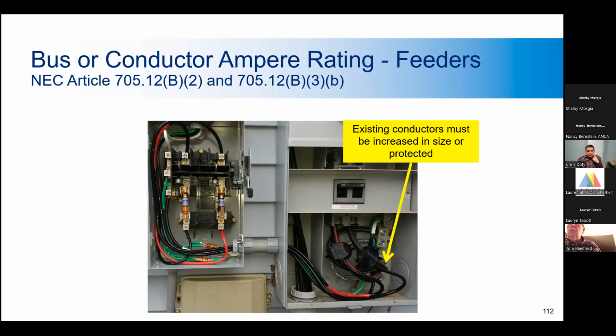You would have the PV voltage tapped into the utility line coming in, and those taps connected to a disconnect. Then you would have a main breaker on your electrical panel so you don't overload your panel. And these are not very common, but there are places where you do see it.